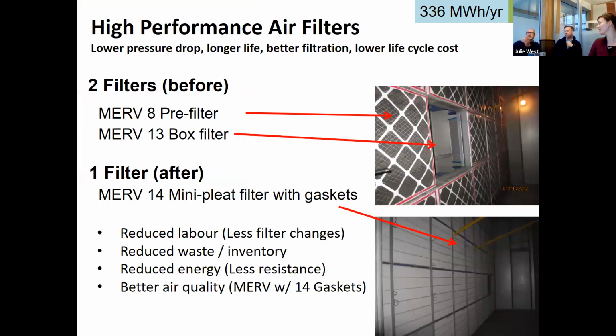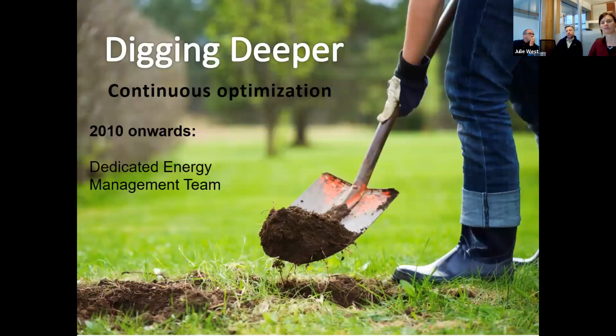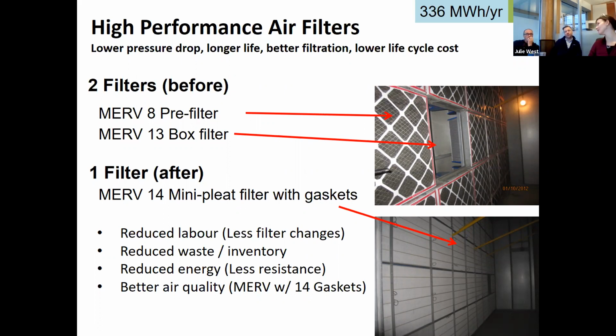Yeah, you're going to talk about filters. Yeah, and so we also changed the filters. Before, we had two filters, a MERV 8 and a MERV 13, and then we moved to one filter after, a MERV 14 mini pleat filter with gaskets. The reason for this is it required less filter changes to change one filter rather than two. It reduced waste in inventory and reduced energy, and this saved roughly 336 megawatt hours per year. Also had us ready for COVID when it arrived.